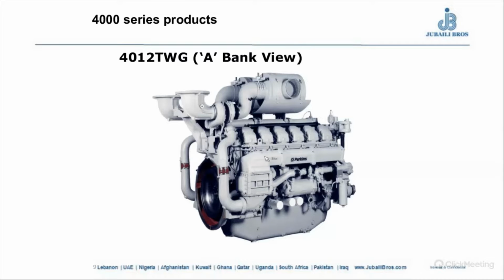The compressed air is water cooled, that's why we have the W, meaning water cooled, not air cooled. We don't have an air cooler on these engines. We have this heat exchanger where water comes in and out. The air comes through the air filter, gets compressed by the turbocharger, gets very hot, comes in here, gets relatively cooled down using the engine water, and then goes to the combustion chambers.